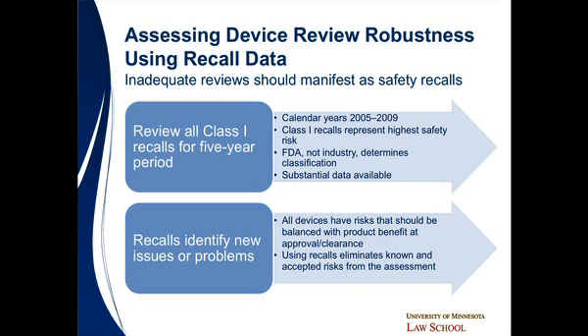We analyzed these recalls for the reason for the recall. And we essentially ended up with 13 categories that fall into 3 broad buckets. One are pre-submission issues. These can be QSR challenges, failures of design control, for example. These can be clinical information gaps, undiscovered risks, post-market problems, manufacturing, sterilization, etc., and a third bucket, which is not really relevant for us, of the counterfeits and the quack products.